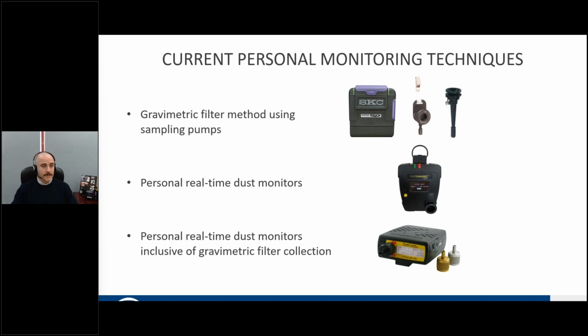Which is one of the key differences between that and the DustCanary. You're able to use a size selective impactor on that device. So it's fantastic that you can get a mass concentration, say on a PM10, PM4, or PM2.5, but you can also look at the spectrum of particles below that impactor size selection.